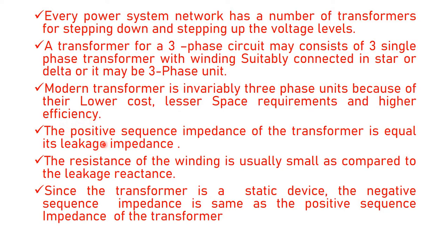The positive sequence impedance of the transformer is equal to the leakage impedance. The resistance of the winding is usually small as compared to the leakage reactance. Since the transformer is a static device, the negative sequence impedance is the same as the positive sequence impedance of the transformer.